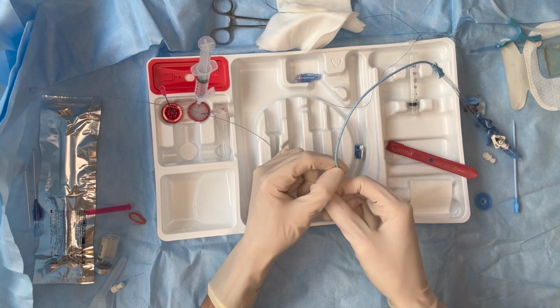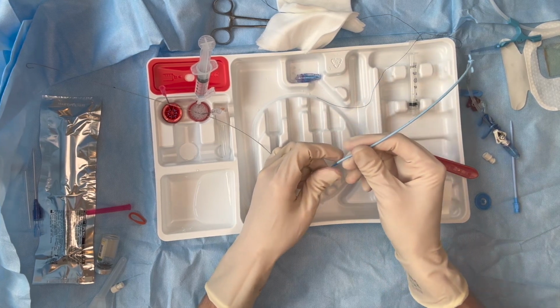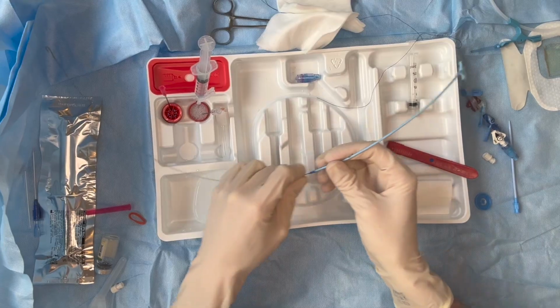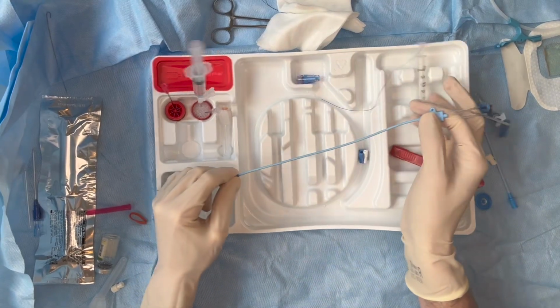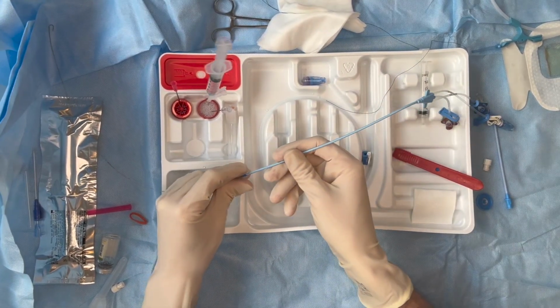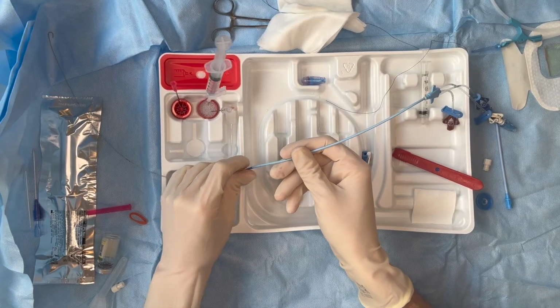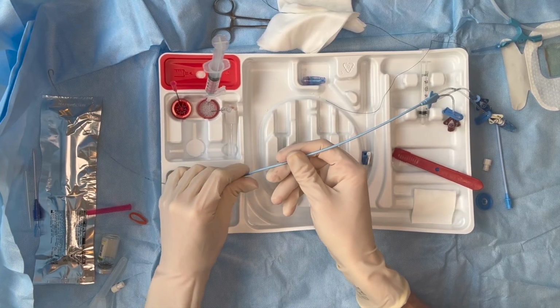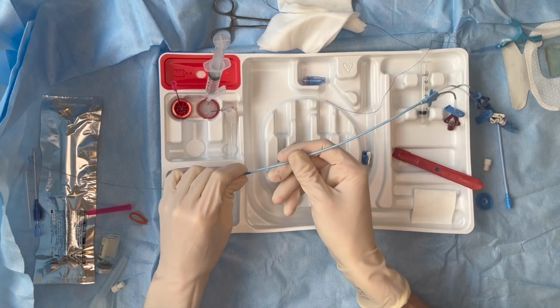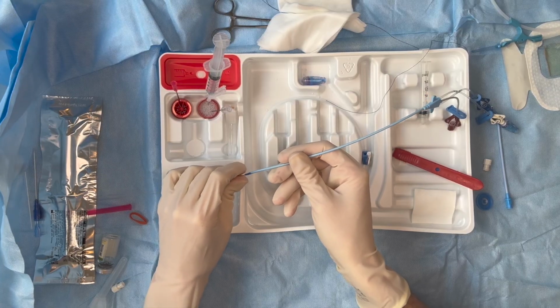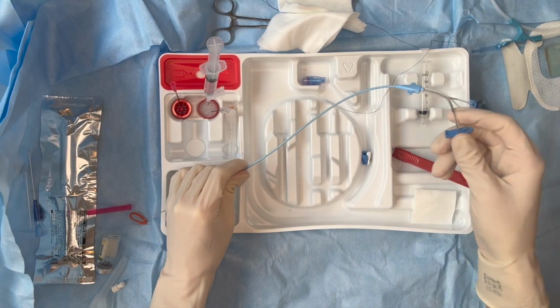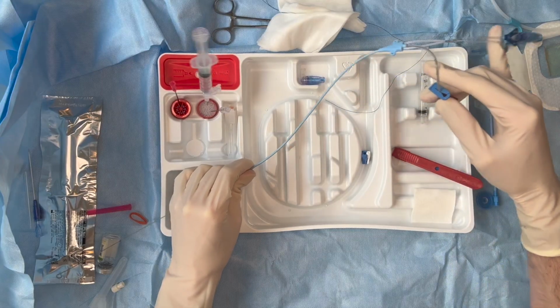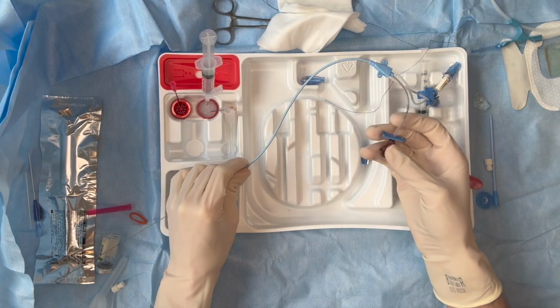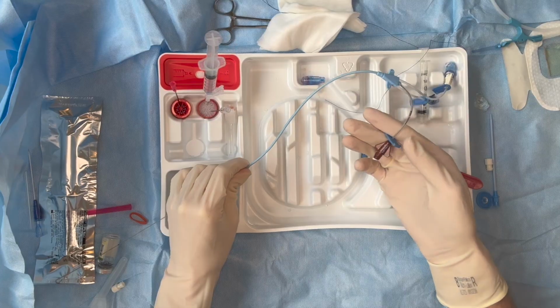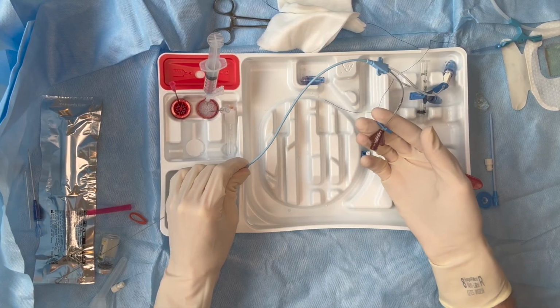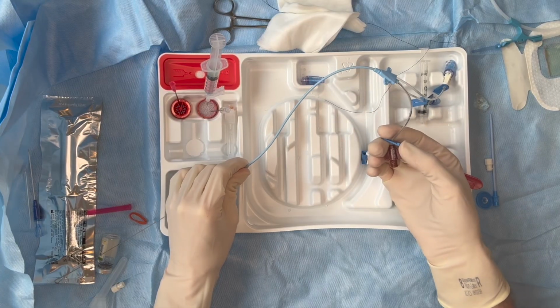And again, that guide wire is going to come out of that middle port, that short one, the brown one. And you just feed it until you see it come out in that clear tubing, and make sure that you're always having one hand on that guide wire. And as you can see, it's coming out there, and then it's going to go ahead and hit that lock that we had earlier to prevent the saline from leaking out. You can just use one hand to go ahead and unlock that, just like that, between your first and third finger, and use your thumb to go ahead and lock it.